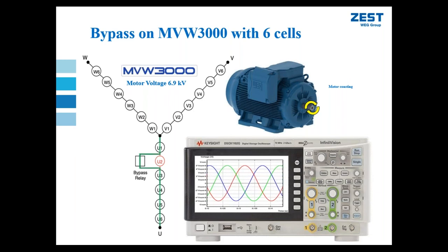So effectively, you can lose one of these power cells and bypass it without having a dramatic effect on the output voltage. In addition, there's another thing that you can do here. You can manufacture a 6.6 kV drive and put seven power cells in each phase. Because this power cell is small and simple, it's literally a little single phase low voltage VSD. It's not expensive. You can add another one in.